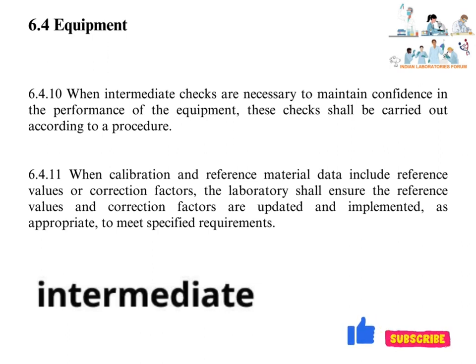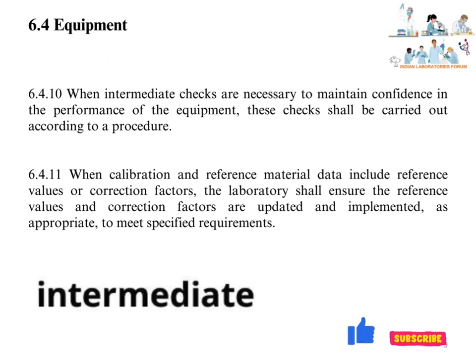When calibration and reference material data include reference values or correction factors, the laboratory shall ensure the reference values and correction factors are updated and implemented as appropriate to meet specified requirements. When a correction factor is reported in the calibration certificate, the laboratory has to affix the correction factor value to the equipment to make the user aware for applying it in regular testing or calibration activities.